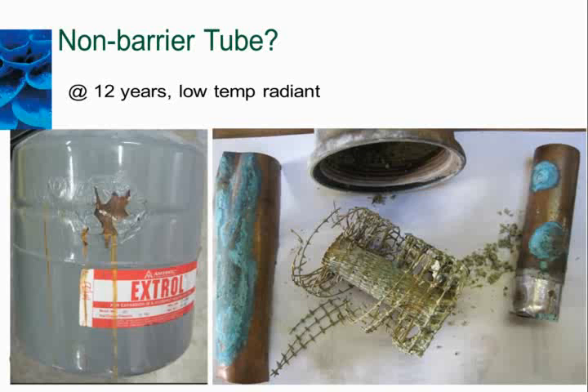This system was filled with just city water, and you can see it completely corroded the media from the air purger, and also pinholed the expansion tank as well as the copper pipe. Anywhere there was copper pipe in the system, it had turned, with green marks on it, and though you can't see it in the picture, there are actually pinholes where those green spots are. Again, I'd say that was an oxygen permeation issue in the type of tubing used, running at elevated temperatures.